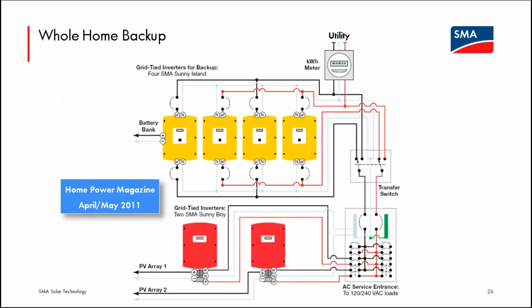Some folks will use the Sunny Island as a full home backup. They don't want to have power from the grid run through the Sunny Island to the loads. They don't want the PV power to have to run through the Sunny Islands. They have the Sunny Islands as a kind of a generator backup.